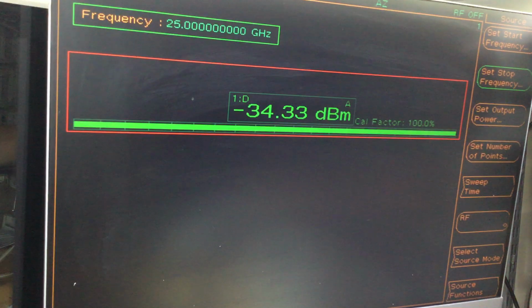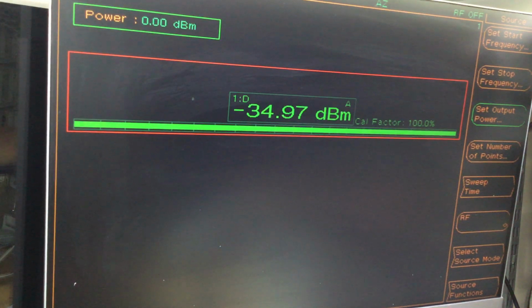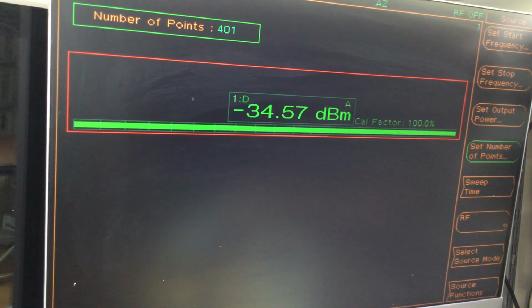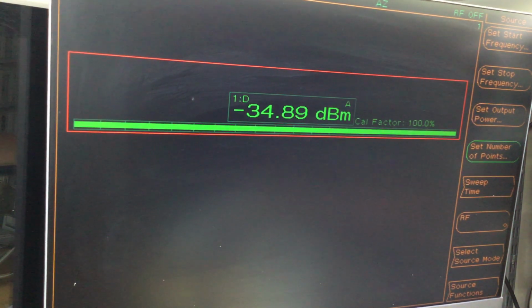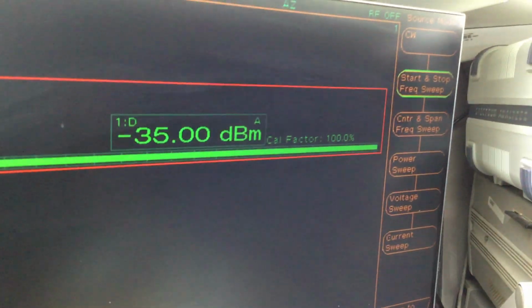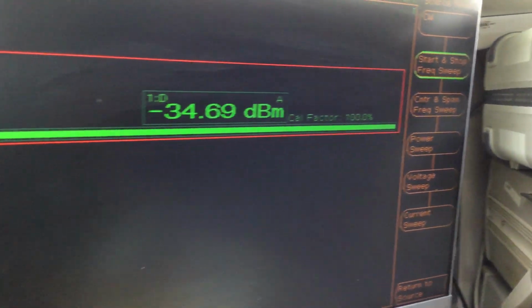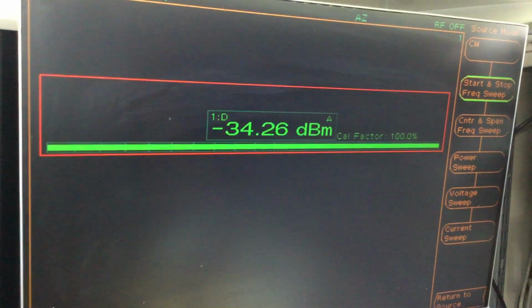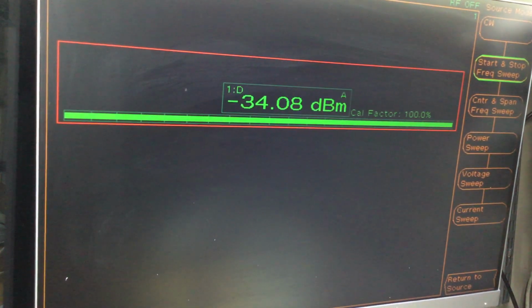Right, 26.5 gigahertz. We'll set the output power as well to 0 dBm, and the number of points 401. We'll leave it at that for the time being. Sweep time we'll leave, and I think under select source mode, yeah, we've got start stop frequency there, so that's all correct as it should be. Right, so now I need to just start the measurement. So I will connect this now up to the RF output lead now on the Marconi test set, and then we'll come back.